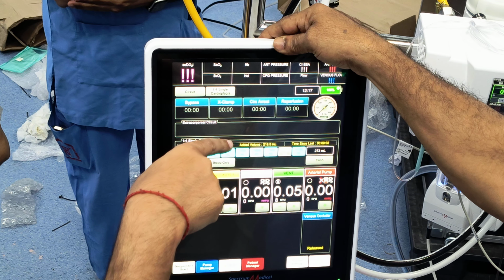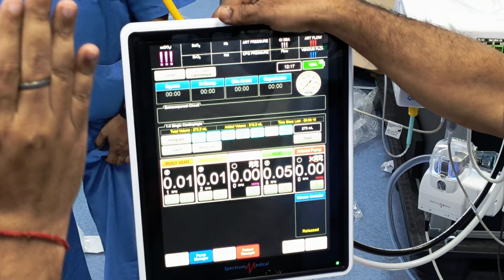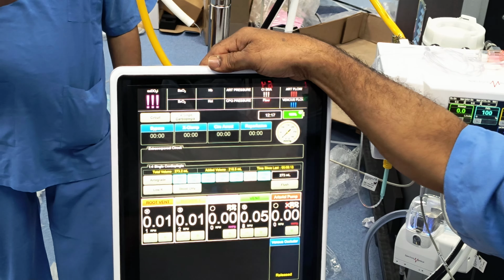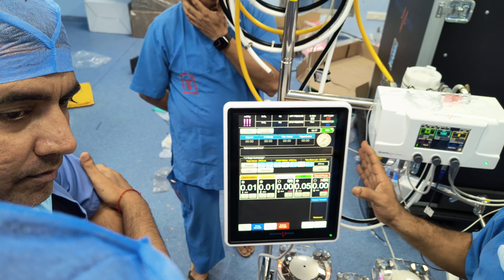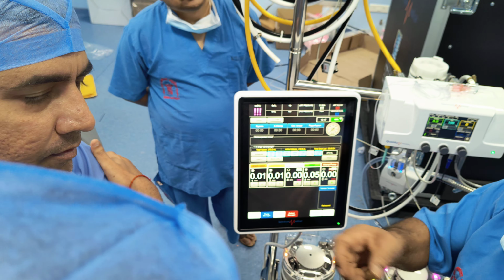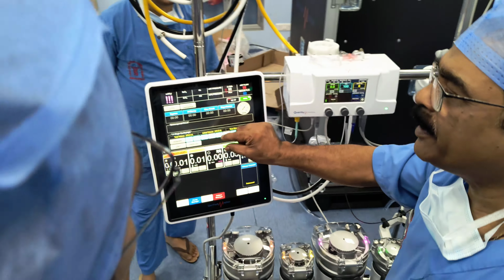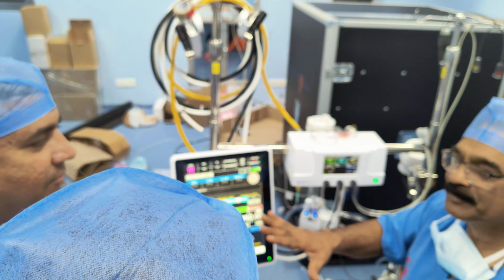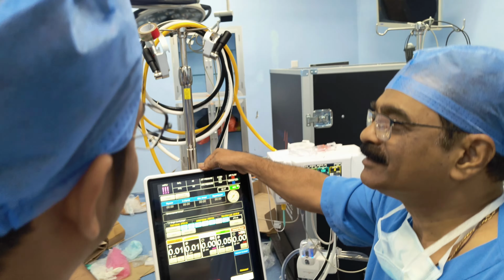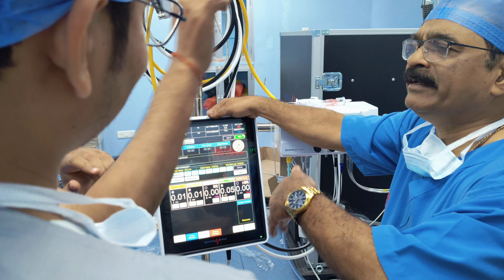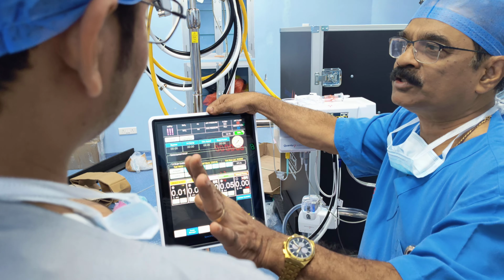How to do it? We have to go into the system settings. The profiling is separate. From time to time the surgeon says stop. We have fed 500 ml, and the surgeon sometimes says stop, just temporary, and then you want to give ostial cardioplegia. So we have a 15-second pause. If you continue giving within those 15 seconds, it will not record as a new dose. If the surgeon takes longer than 15 seconds to change the ostial, say he wants 2 minutes, then it will register as another dose.